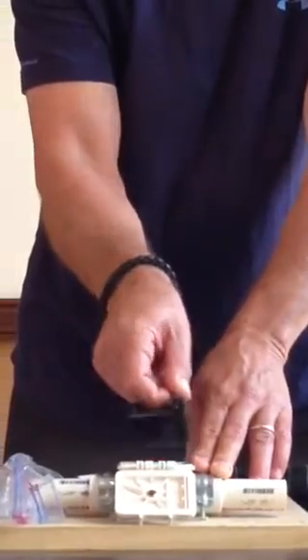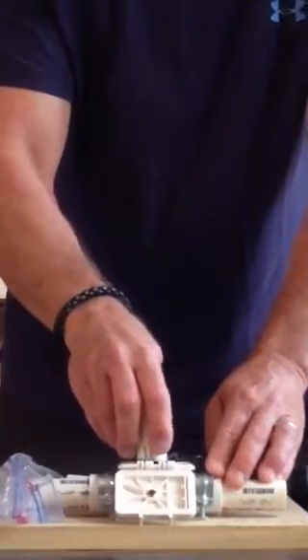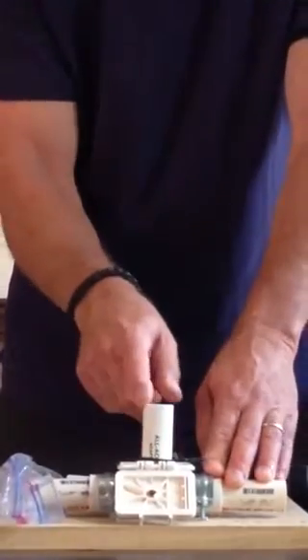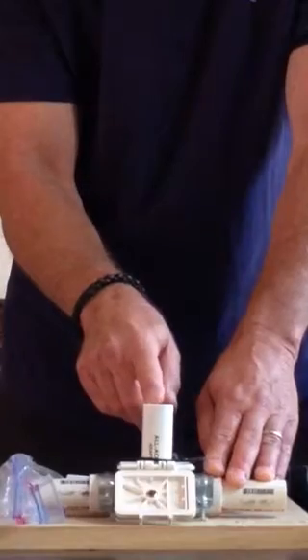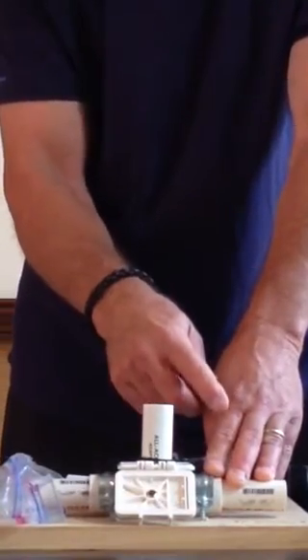Now you can take this flapper assembly out. It removes easily. It comes with an adapter. This adapter goes inside the drain here, and now you can vacuum out the line from this side, or you can put more air pressure in to blow out the line into the unit.